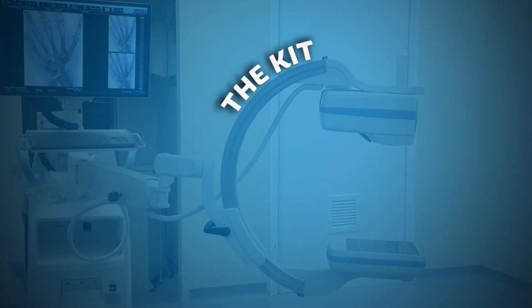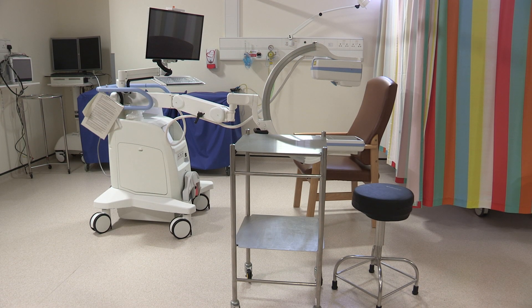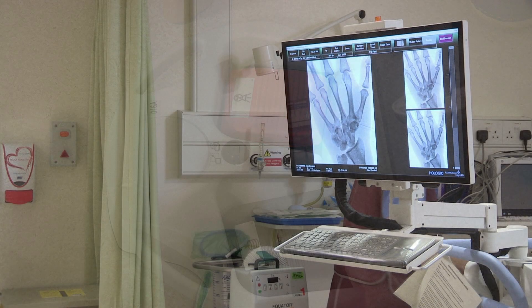The kit: we have a Hologic Image Intensifier, though there are many other models available — make sure you are familiar with the one in your hospital. Basically, a Mini C-arm has an X-ray generator, an image collector, an adjustable arm, foot controls, a screen, keyboard, and printer.